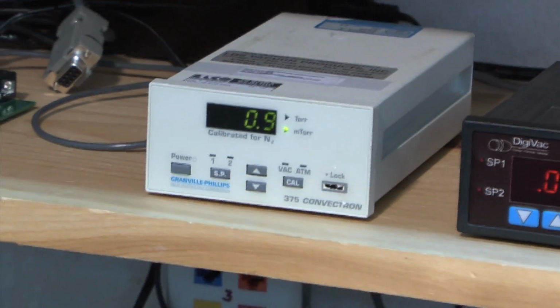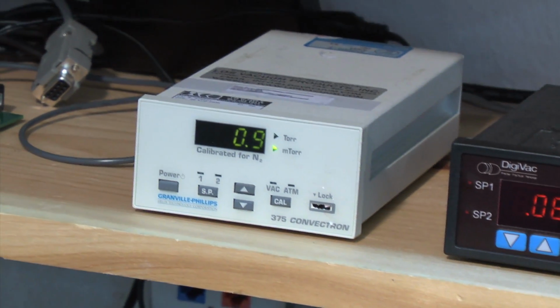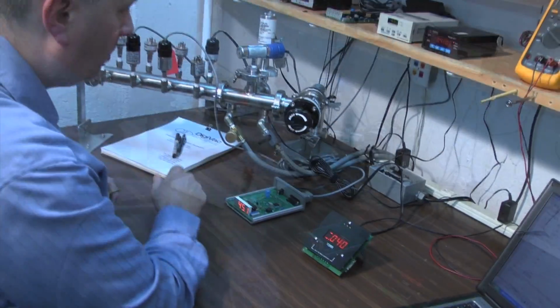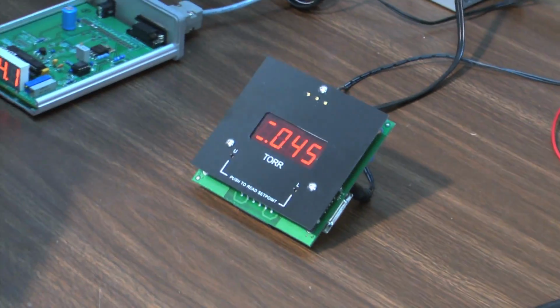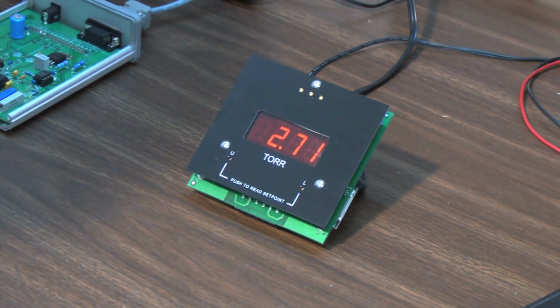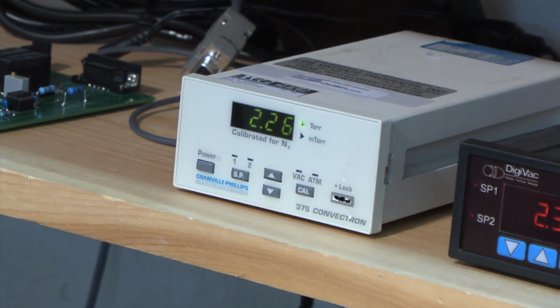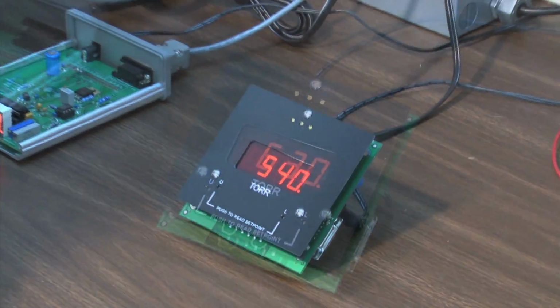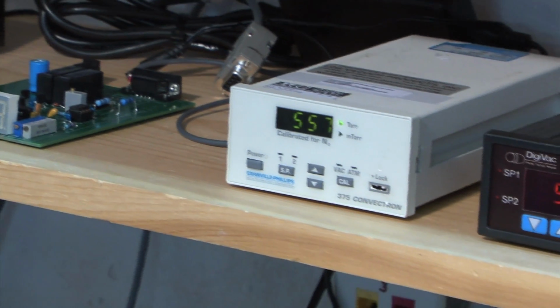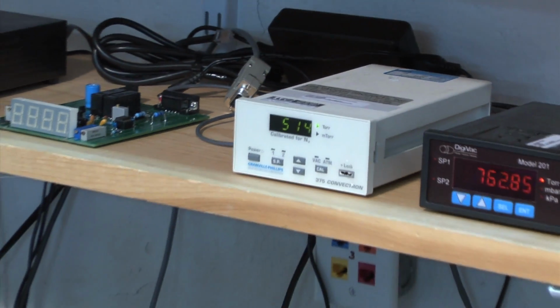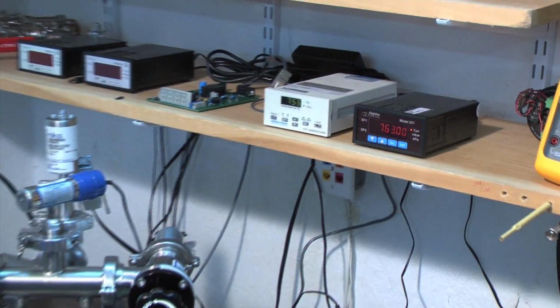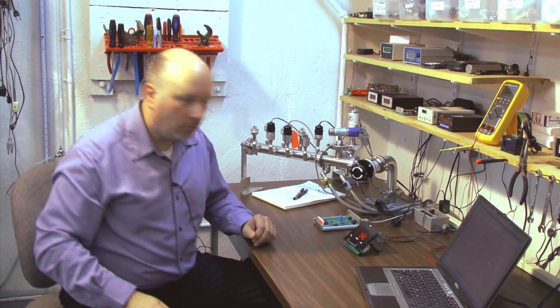We'll stop our system, and we'll take a few more readings, increasing pressure. Approximately 43 millitorr, 42. 2.26 torr, 2.69 torr. Acceptable. We'll go and look at our high end again and see how well we control up high. 560 torr, 540 torr. And my last check for calibration is to vent my system all the way to atmospheric pressure and make sure we're reading approximately 740 to 760 torr, and we are. This is our properly calibrated DigiVac 801W vacuum gauge.